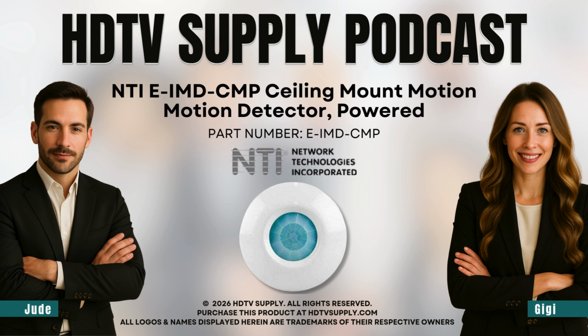So once you trust that signal, you have to actually wire it in. What's the physical installation like? Is it complicated? No, they designed it to be pretty straightforward. It just uses standard screw terminals, for a 22-gauge two-wire cable that connects to the digital inputs on the EIMDCMP. What's interesting is the maximum cable length, which is 1,000 feet. So you could run this across a massive campus. And it comes ready to go with its own 12-volt power supply.